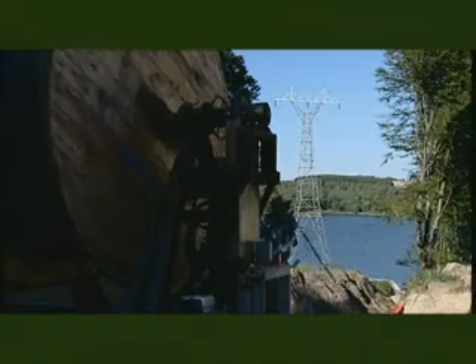The earthing cable is pulled through one pipe, together with the high voltage cable. This presents no problems with regards to tensile force. The earthing cable runs through the pipe laying to the west. With directional drillings, as well as with pipes running along the bottom of the inlet, the cable is protected against damage by using rollers at the lead-in to the pipes.